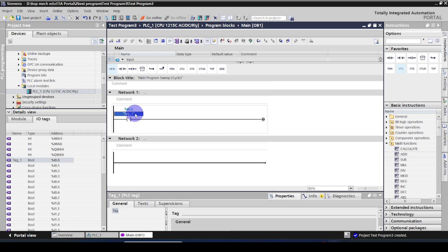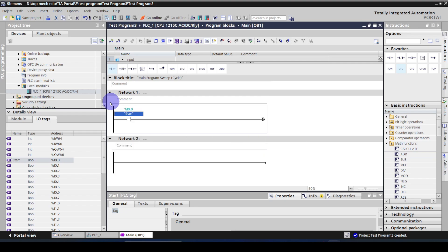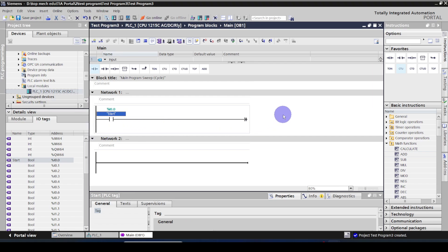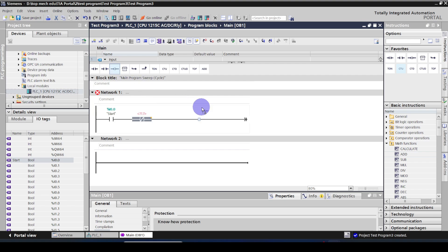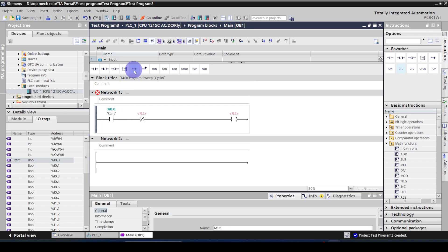The default tag name is Tag 1 — you can give a custom name for this memory location. Right-click and select Rename Tag. I am going to rename this memory location to 'Start'. Always try to give a relevant name to increase the readability of the program. To complete the latch circuit, I am going to add the normally closed contact for the output, and also an optional parallel path for the latch.